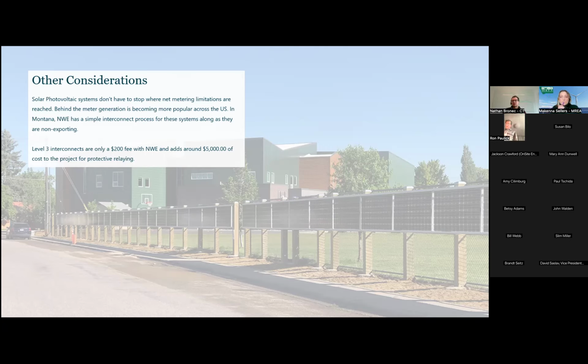But anyway, the battery aspect hasn't really kicked off too much in Montana. We've done some bigger, multi-megawatt battery projects, but the owners of those are looking at them as grid assets versus building assets. What I mean is they're entering the marketplace and waiting for ISO controllers, grid managers, to send dispatch signals saying, hey, our grid is peaking right now and we need more generation online, so they send a dispatch signal to the batteries to do that.